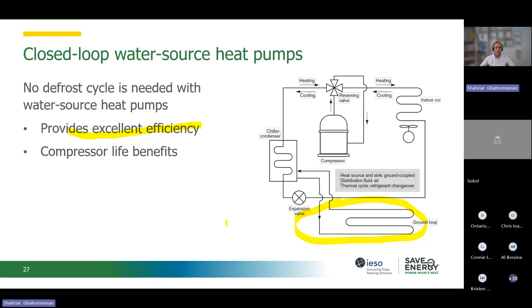The same thing for the ground as well. The ground temperature across the GTA, in the projects that I worked with, is 8 to 10 degrees Celsius. Again, it's a constant temperature. But when outside is minus 10 degrees Celsius, the COP or efficiency of our heat pumps becomes lower actually. And that's why, again, the efficiency of our heat pump goes down. So that's the reason: we depend on the outdoor weather with an air source heat pump, versus the water source heat pump or ground source heat pump, which typically work with an almost constant temperature in the ground and a little bit of variation for the water source heat pumps actually.